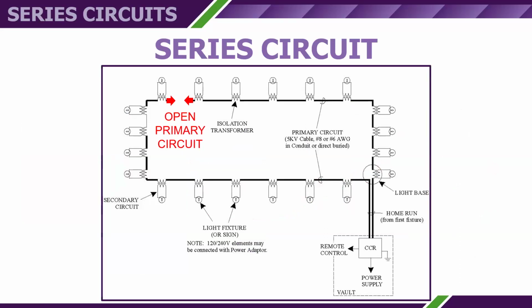Let's talk about some series circuit characteristics. First, we'll talk about what happens when we get an open primary. All the lights go out. In an open primary, no current flows, and the lights are out. The constant current regulator sees an open circuit as an increase in load. It will raise the output voltage with the load to try to maintain 6.6 amps of current flow until it reaches the maximum open circuit voltage. It's an overvoltage and it trips the constant current regulator offline.